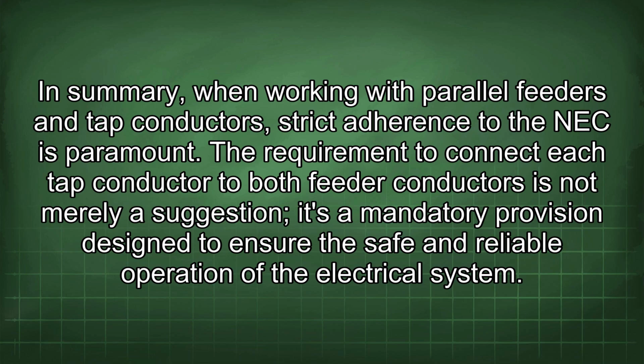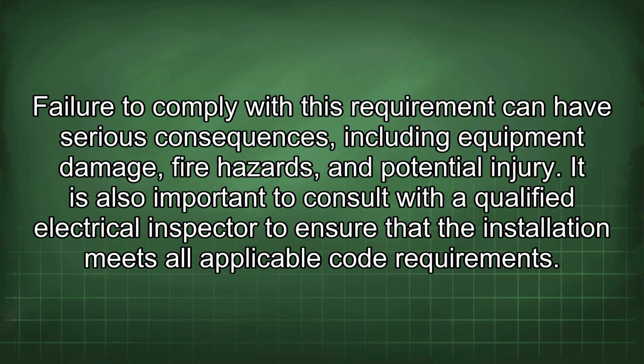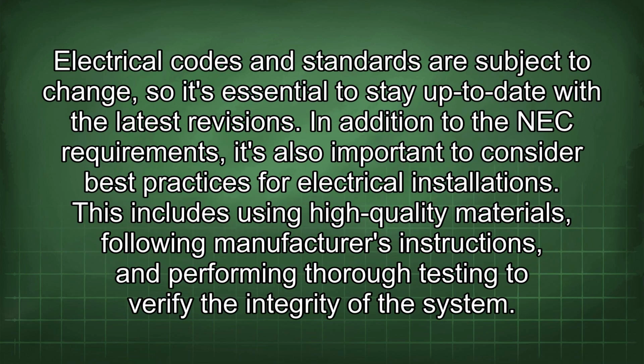In summary, when working with parallel feeders and tap conductors, strict adherence to the NEC is paramount. The requirement to connect each tap conductor to both feeder conductors is not merely a suggestion, it's a mandatory provision designed to ensure the safe and reliable operation of the electrical system. Failure to comply with this requirement can have serious consequences, including equipment damage, fire hazards, and potential injury. It is also important to consult with a qualified electrical inspector to ensure that the installation meets all applicable code requirements. Electrical codes and standards are subject to change, so it's essential to stay up to date with the latest revisions.